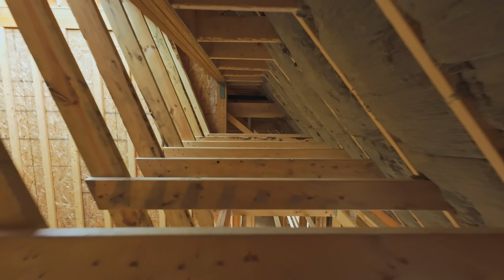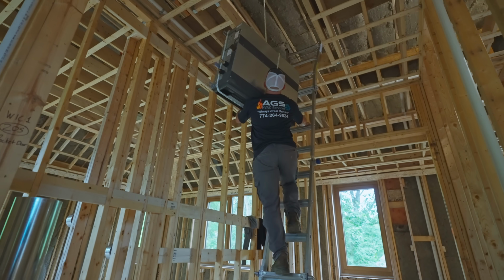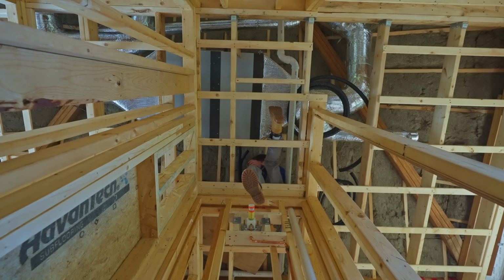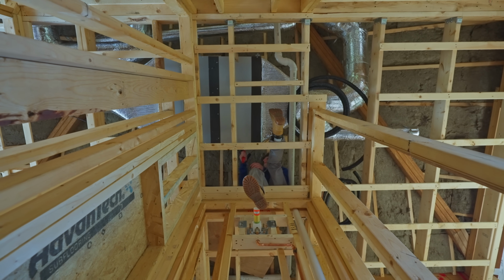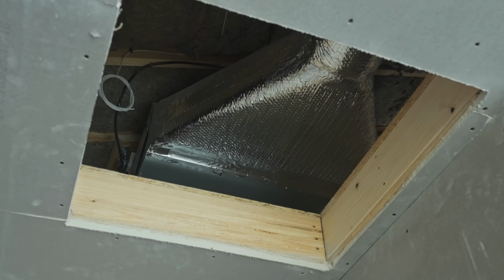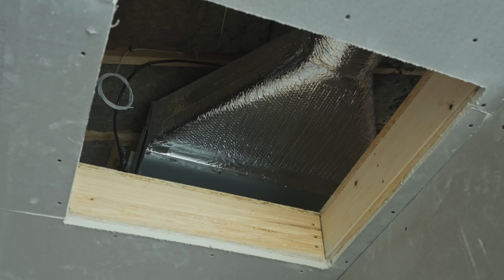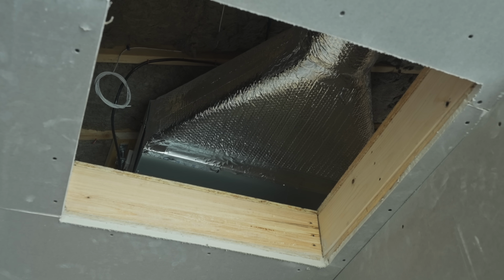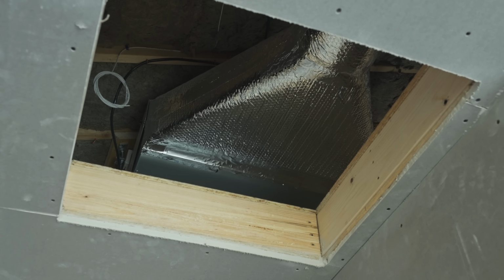Since we didn't have much room for ductwork, the Mitsubishi came in really handy with the PEADs, the high static pancake air handlers. Putting them up there, facing them a certain way, so that when our service guys come through the hatch with their filters, they're only taking the filters up there with them.